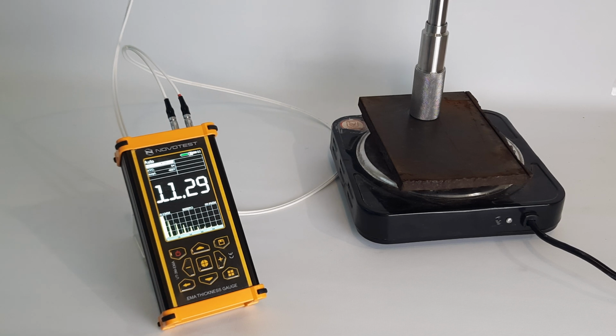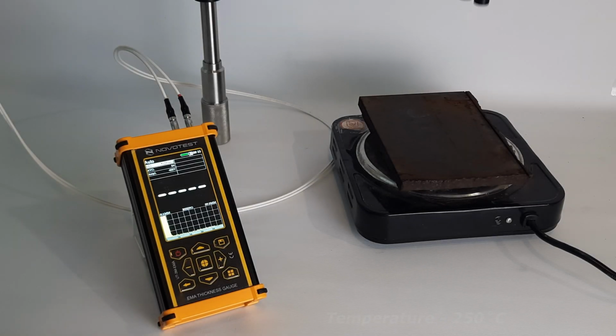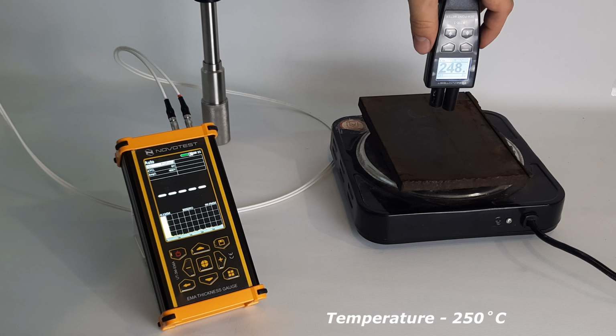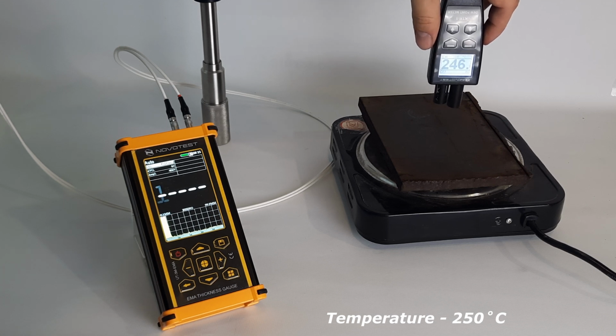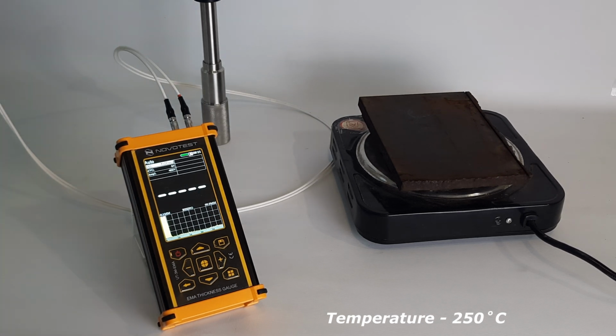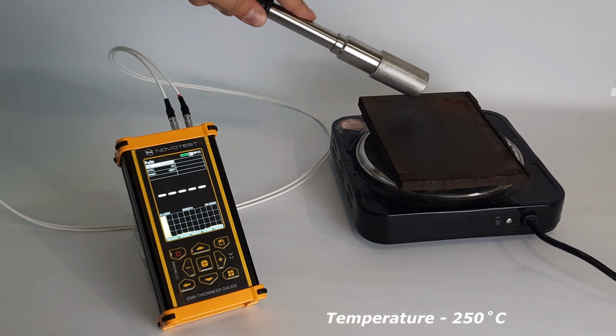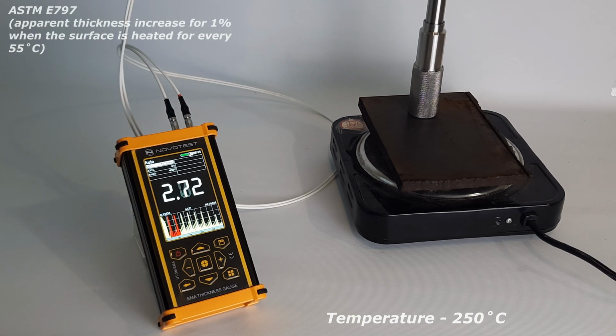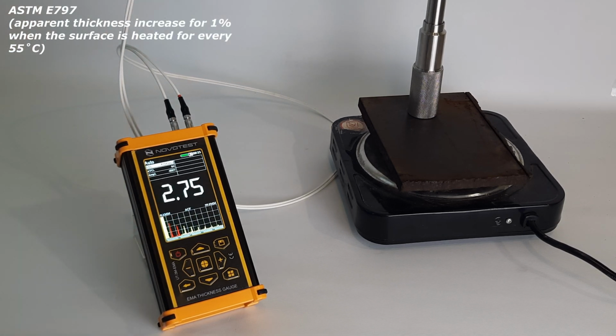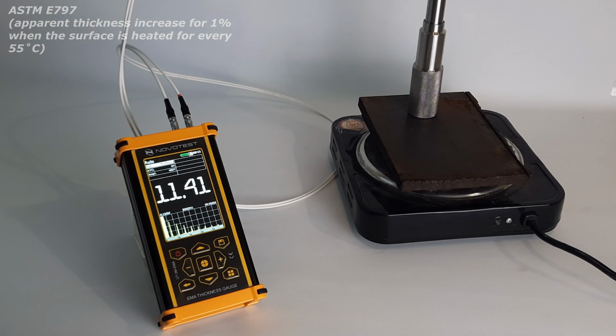As you can see, as the temperature changes, the thickness reading changes as well. The thickness reading on the screen changes because of a set of different factors. According to the ASTM E797, there is a rule of thumb which states the apparent thickness is increasing by 1% as the temperature of metal rises by 55 degrees Celsius or 100 degrees Fahrenheit.